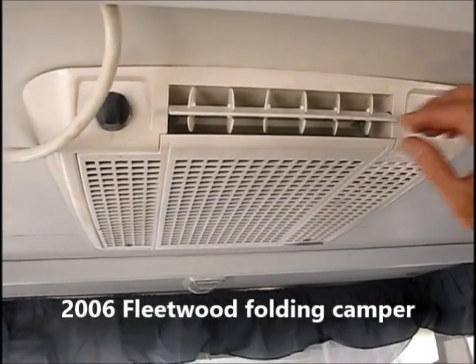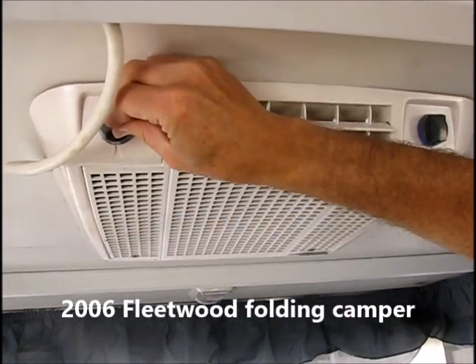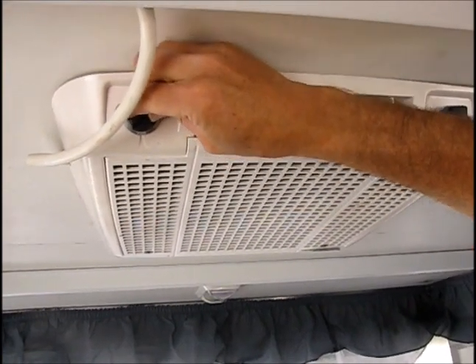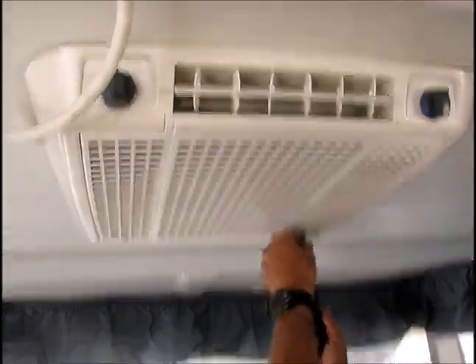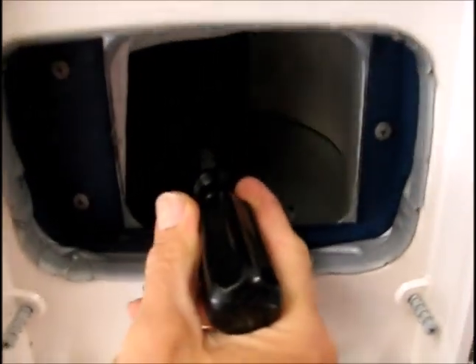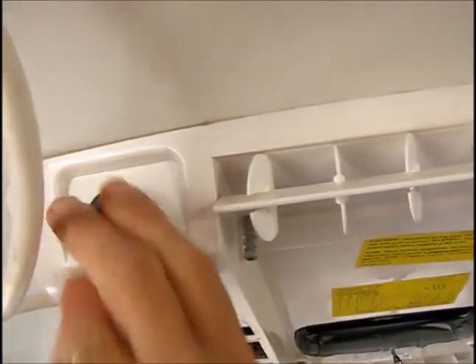The problem with this air conditioner in this RV is that when we turn the fan on low, it just hums — it's not firing up, and if you leave it on it's going to trip a breaker. So it's drawing current. We're going to take this cover down. On this model it's just a couple of retaining screws — pull it forward. I'm going to see if this fan spins, and it does spin. Now if we turn it on — there it goes. So this is pretty much a classic start capacitor issue.